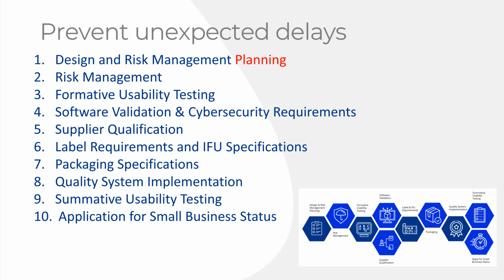For summative usability testing, it is not just write a justification for why we don't need this, or find 3 users, do a bioskills lab, and you're done. That's not how it works. Pretty much any device with an electronic interface, a digital interface, is going to require more involved summative usability testing than you are prepared for.